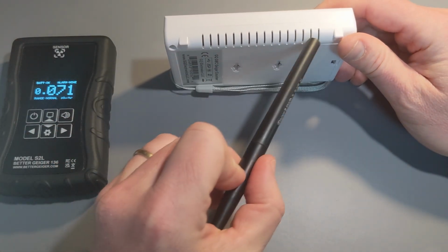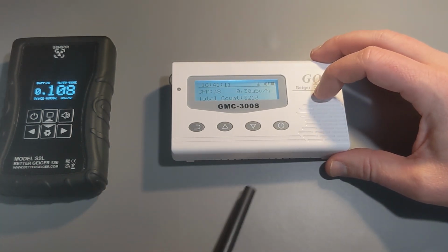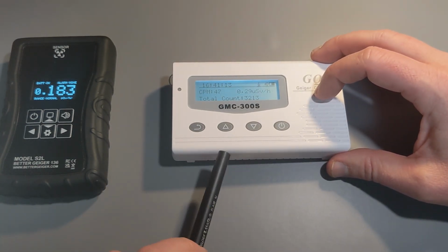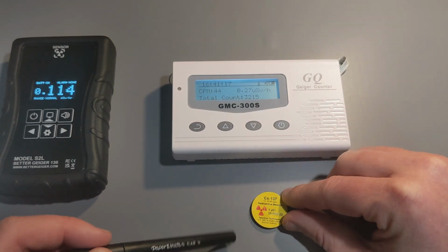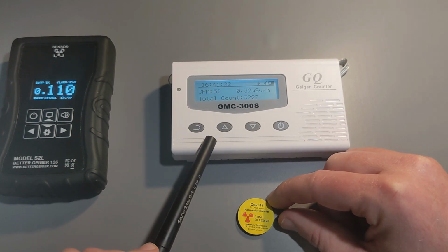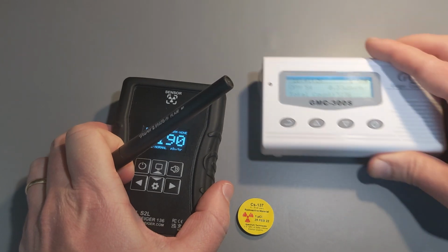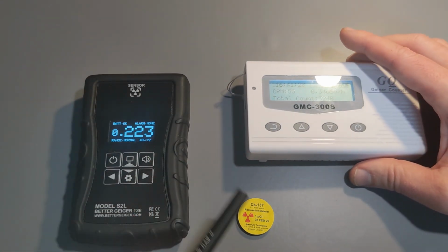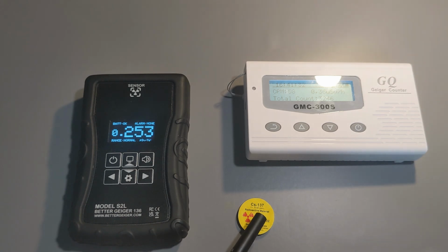So it has a tube here. All it is doing is counting. So if it gets a low energy or a high energy, it'll pick it up and say, well, we got a count. And these are typically calibrated to cesium-137. So if you measure with cesium-137, it's going to be pretty accurate. But if you have a different energy, it will generally not be. Mainly this comes into play because this is a pretty high energy, and most realistic scenarios tend to be on the lower side.